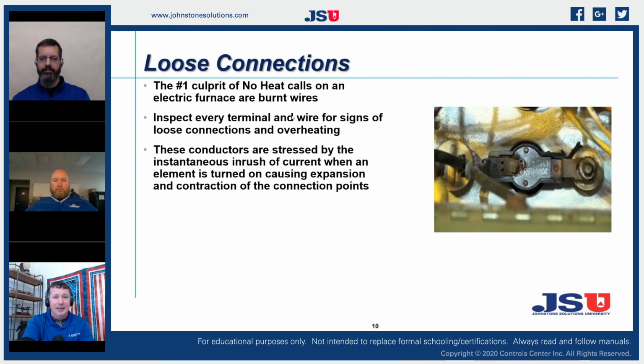One thing that we run into a lot is poor connections, which generates heat. So anytime that we change the resistance of a connection, when we turn a conductor into a resistor, we're going to generate heat. And because we have so much current passing through our components, they're going to be the ones that are most likely to generate that heat. So anytime we see a heat source from a conductor, that part needs to be replaced.